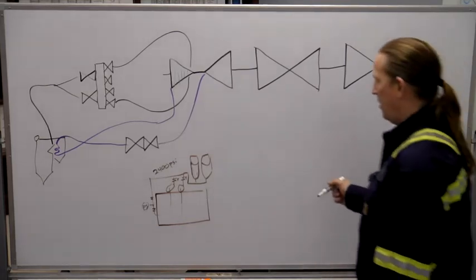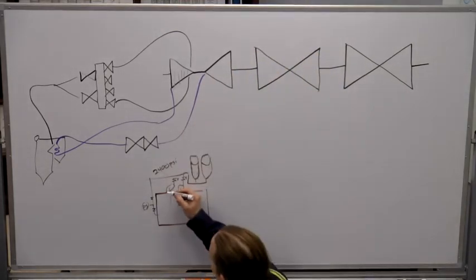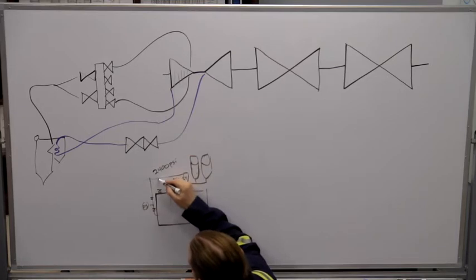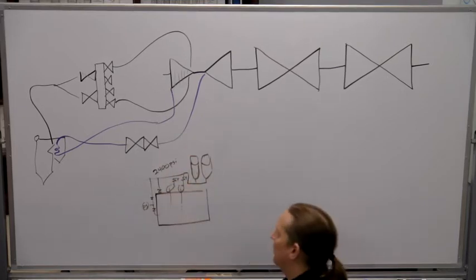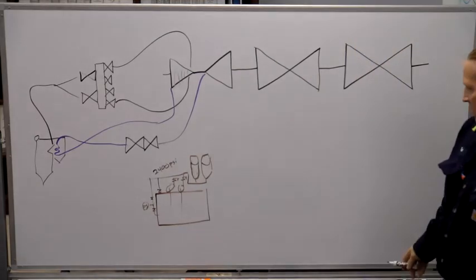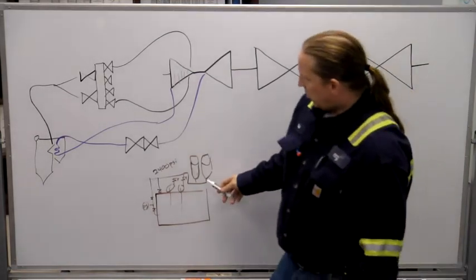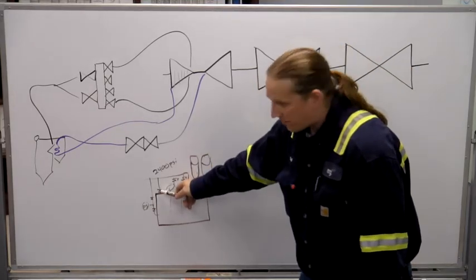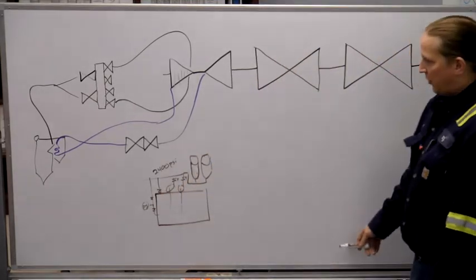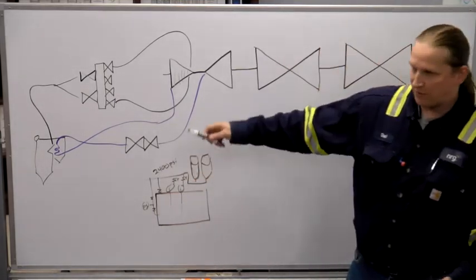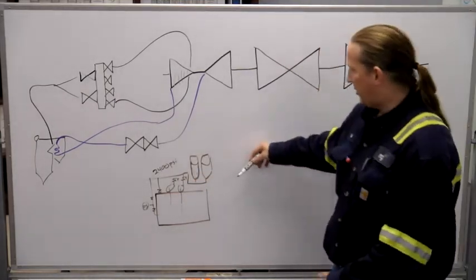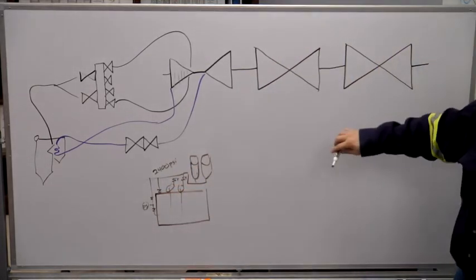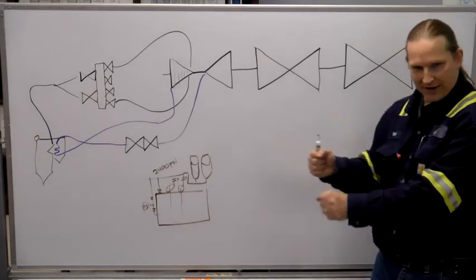There's also a manual bypass valve. When you start the pumps, this bypass valve should be all the way open so that you don't have the pumps trying to slam 2,400 pounds of pressure into the system. Then they start and you pinch back on the bypass, and when pressure starts to climb you slow down and ease it all the way shut.